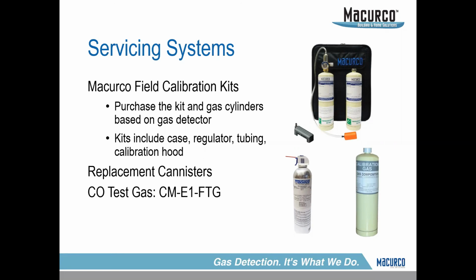If you're in Nassau County, it happens all the time. Florida, we're seeing it quite often. Georgia, we're seeing it often too. And California obviously is the same thing. Everything's here, but the one thing I do want to stress is there's a difference between testing and calibrating. A test is just to see if the sensor recognizes gas. A calibration makes sure the sensor and circuit board are speaking the same language. It's very different, just so you guys know.